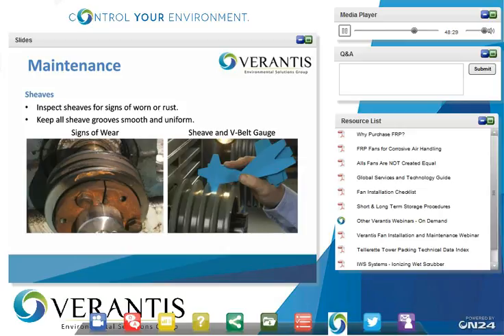Sheaves: inspect your sheaves for signs of wear or rust. If you've had a fan sitting for a while, outdoors or in a high humidity area, that hasn't been running, you can potentially get rust on the sheaves. You start the fan up and start running, that rust is going to start chewing on the belts, and over a period of time it could potentially cause premature belt wear. So you want to make sure all the grooves are smooth and uniform.